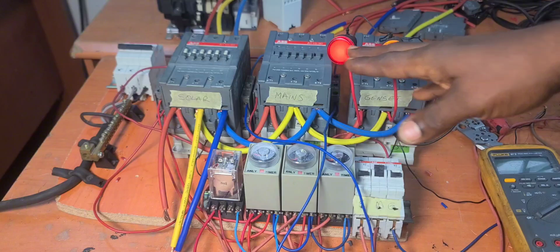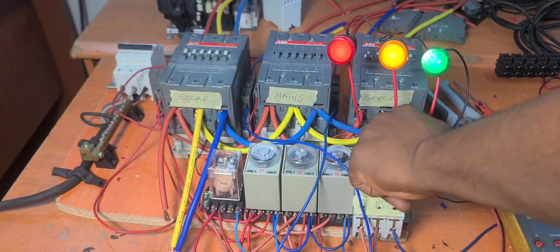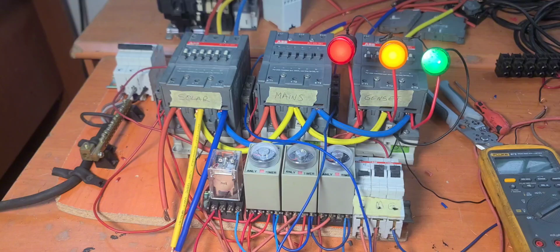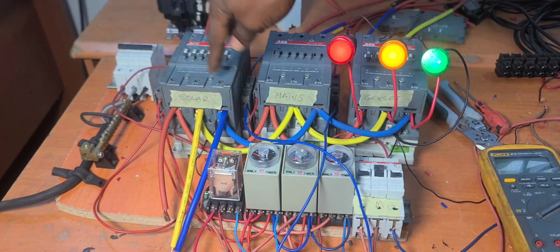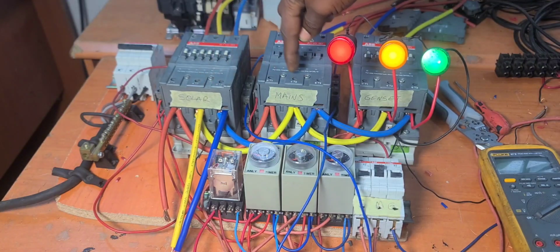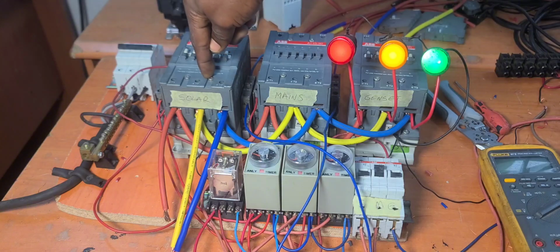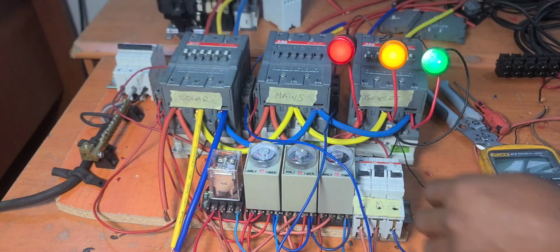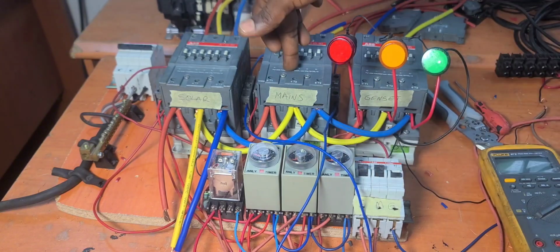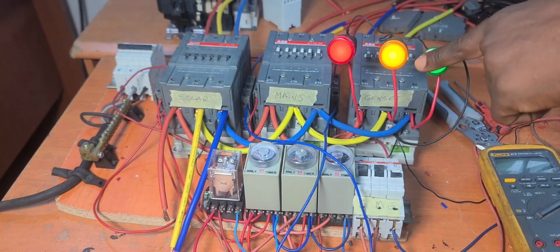So when it comes up that way, we have our load here. This one cannot work, even if we put it on. Cannot work, even if we put it on. It's just going to be idle. But in the process, while this one is running, if solar comes back up, immediately solar comes back up, it cuts off power from mains. And then it delays for some seconds and it connects power back to the load from the solar. So let us activate this solar again and see how it behaves. You see, it has disconnected this one immediately and it is waiting. This one will make, and then we have power on our load.